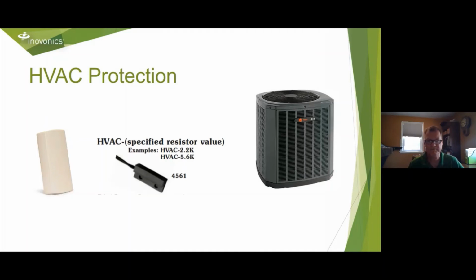GRI makes a very simple tilt switch for this called the HVAC 2.2K. If you use our EN1210 EOL, which normally uses a 2K resistor, you won't need the resistor anymore because it's built into this tilt switch. It fits inside the HVAC unit. If you take the cover off to get to the copper, you'll get an alert, and the wiring out to it is totally supervised. You can put our transmitter in a weatherproof box — I recommend either a deep single gang or a 4x4 — and our transmitter will fit right in there.